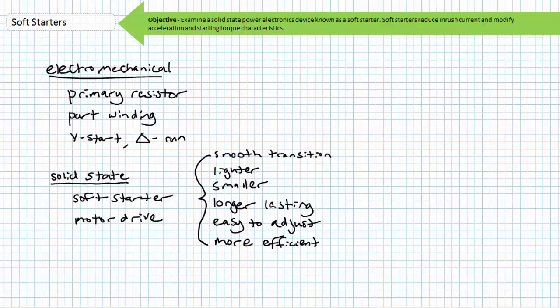A soft starter, among its many abilities, can smoothly ramp applied voltage from a predetermined start value to full voltage over a customizable period of time. This smooth voltage ramp yields more precise control of starting current and torque. Additionally, soft starters are often smaller, lighter, longer lasting, easier to adjust, and more efficient than their electromechanical equivalents.